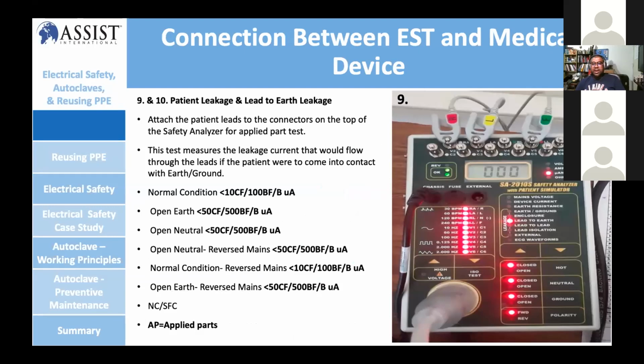So when you do an applied part on a patient, for example, you can see in this particular setup we have the ECG line installed. When the ECG line is installed, for CF it should be 10, and BF 100 and B 100. So this is the range that you're going to work with. And you can see all the LEDs. That means the LEDs are showing you are measuring the particular applied part in the group.